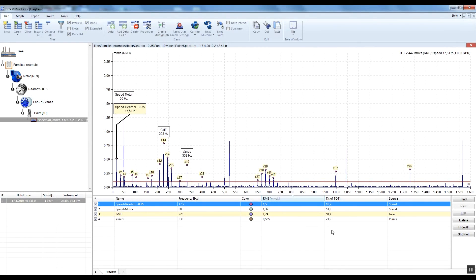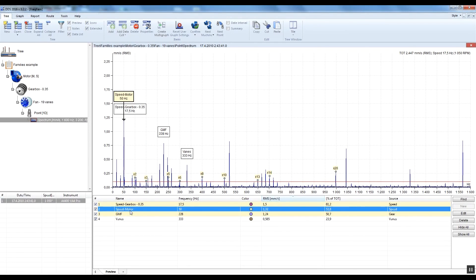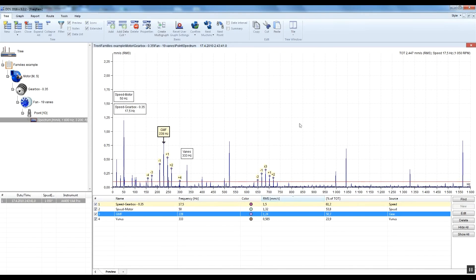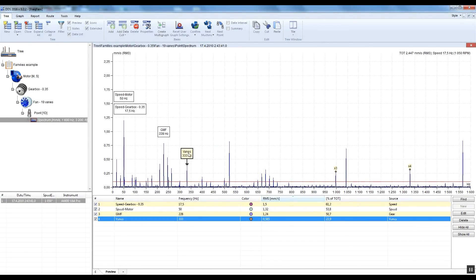You can select each family in the list. Here is the motor speed family — you can see the carrier frequency and harmonics. Here is the gearbox family with carrier and harmonics. GMF family with carrier frequency and sidebands in this case. And the vanes family with carrier frequency and third and fourth harmonics. The second harmonic is probably present but not labeled because it's too low.